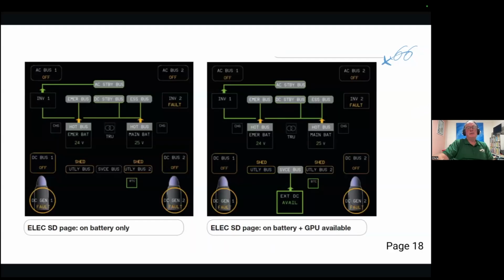Here are some displays on how the system is indicated or displayed. In the left one, you see the electrical system display is only the battery is on. The two batteries are on as long as the bus tie contactor is in operation - in other words, it's making everything available, and through to the inverter, I can have a little bit of AC as well. I've inverted DC into AC now, and that will supply the AC standby bus.